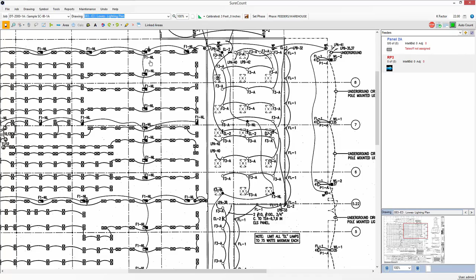Now, the first thing is the scope of the job: add a new feeder and transformer and panel board to have a 200 amp, 120-volt panel board, a 75 kVA transformer, and a 480 volt feed from the existing electric room here, and then some branch circuits that for now are just going to feed some new lighting in this area of the store.